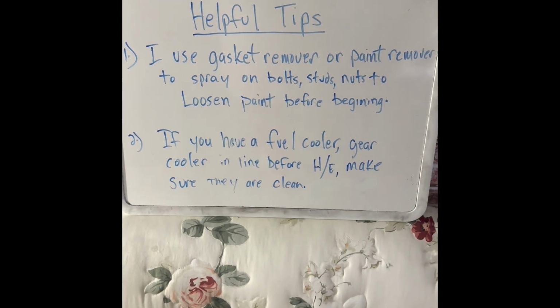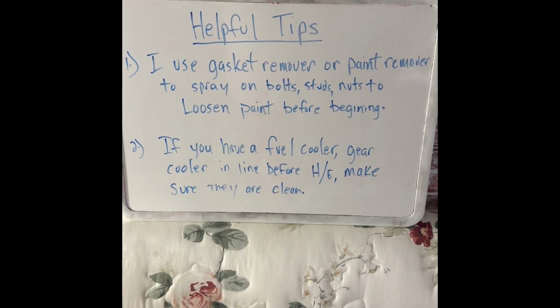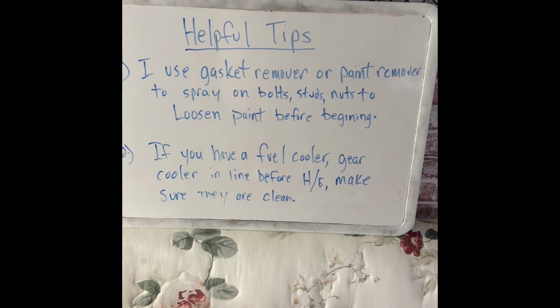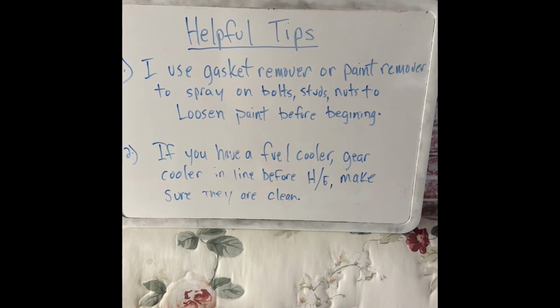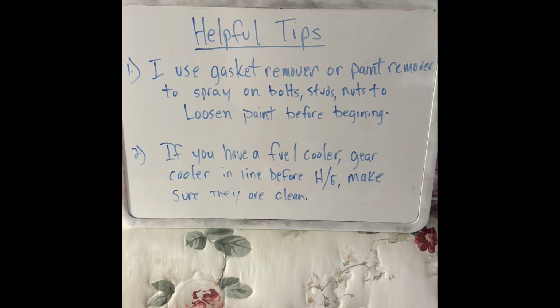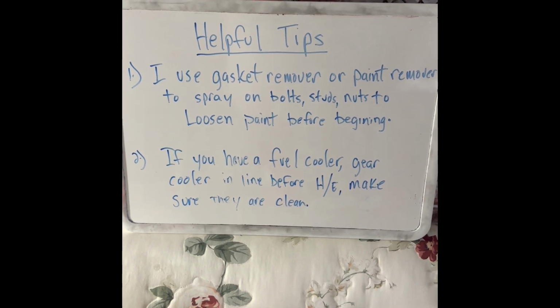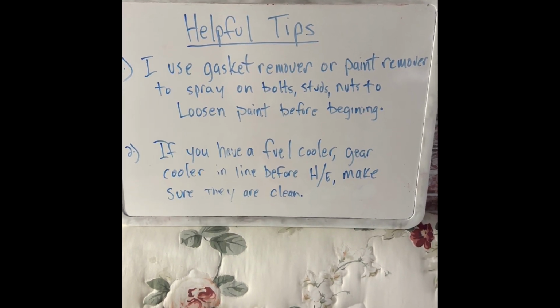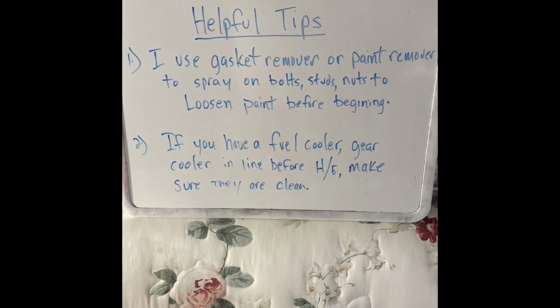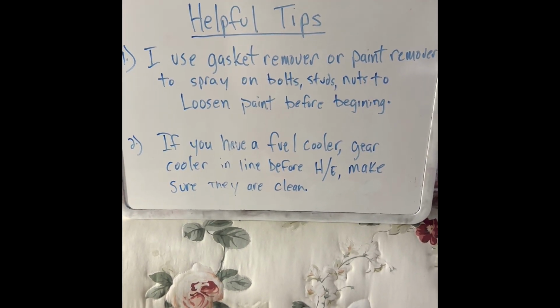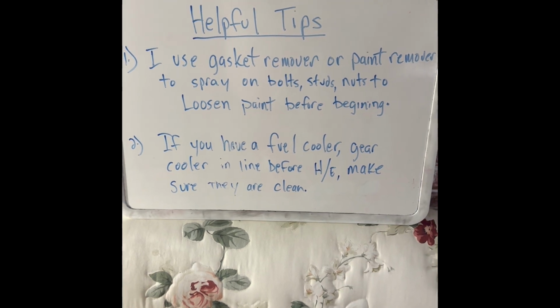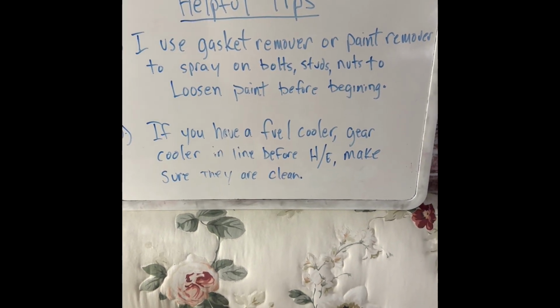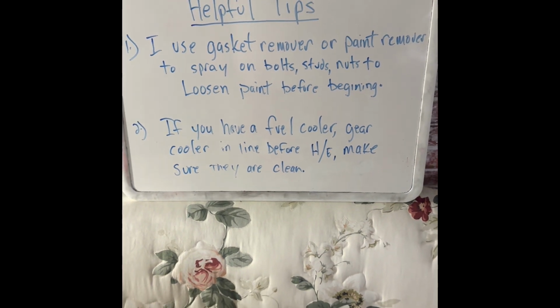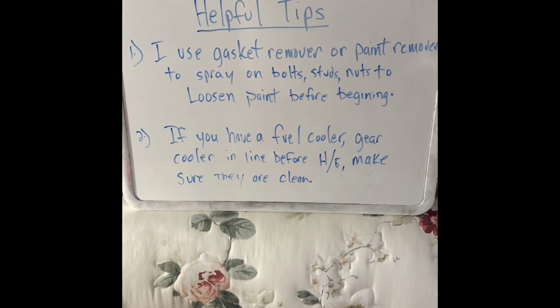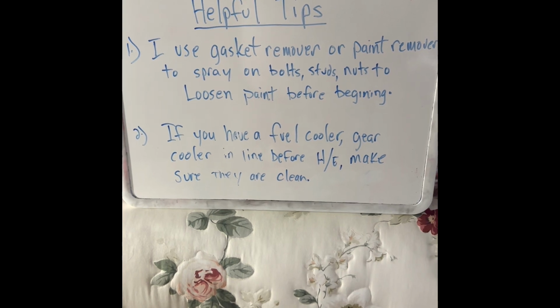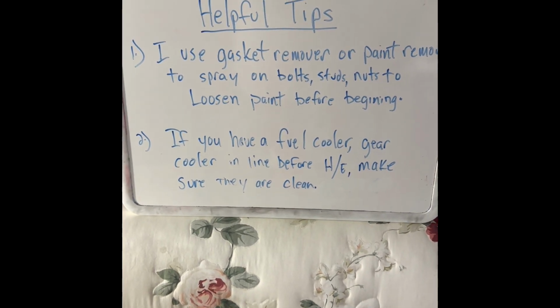Okay, some helpful tips before you start your heat exchanger clean job. I use gasket remover in a spray can, and I spray down the nuts and bolts that are all around the heat exchanger, and it loosens the paint and makes it a lot easier to come apart. And I usually put in new bolts and lock washers when I put it back together. If you do have a fuel cooler or gear cooler, you might want to make sure that it's clean and not restricting flow going to the heat exchanger.